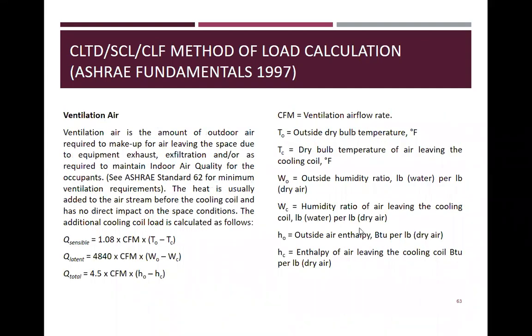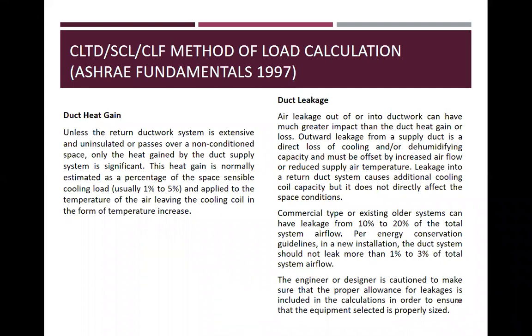Okay, outside air enthalpy. Next is the duct heat gain. Unless the return ductwork is extensive and uninsulated or passes over a non-conditioned space, only the heat gain by the supply duct is significant. This heat gain is normally estimated as a percentage of the space sensible cooling, usually 1% to 5%, and applied to the temperature of the air leaving the cooling coil in the form of a temperature increase.